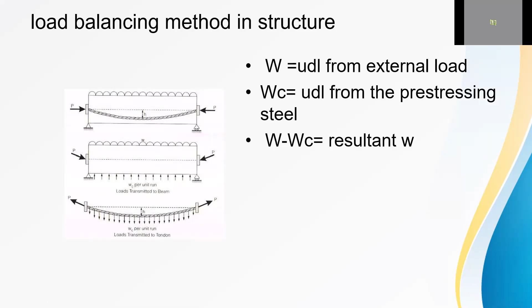The usage of the load balancing method can be seen in the continuous beam. Before applying the load balancing method, we can see the live load, the red one, and the blue one, which is the dead load. After applying the load balancing method, we can see inside the concrete beam the cable. The cable is deflected following the cable profile, and this is the resultant distributed load, which we can see at the support. It shows an upward load because the rectangle here is placed on the upside, while the remaining span, which is not at the support, goes to a downward load.